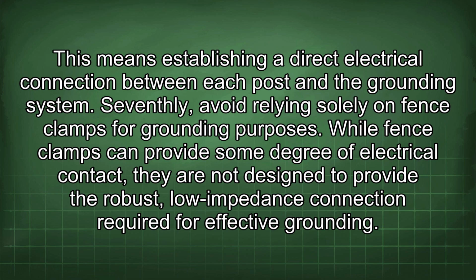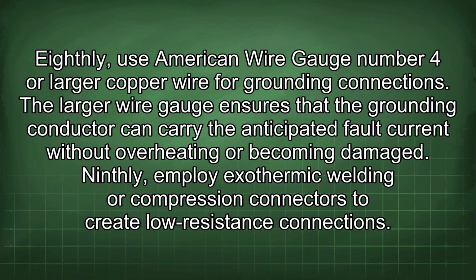Seventhly, avoid relying solely on fence clamps for grounding purposes. While fence clamps can provide some degree of electrical contact, they are not designed to provide the robust, low-impedance connection required for effective grounding. Eighthly, use American wire gauge number 4 or larger copper wire for grounding connections. The larger wire gauge ensures that the grounding conductor can carry the anticipated fault current without overheating or becoming damaged.